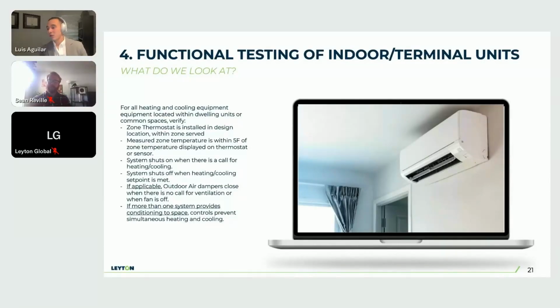And then the fourth test that we also take a look at is the indoor terminal unit. So these are what we call the split system units, the PTAC units. These are very common, sometimes to aid or help the main system. So sometimes you'll see them in a specific room that may be getting hot, maybe because the diffusers are not balanced. That may be an issue. Or maybe it's just an undersized unit, maybe built from a long time ago. It's very old, so it's no longer adequate. We see them in homes that are older, and they'll add one of these to their rooms. But we also see them in new constructions as well.